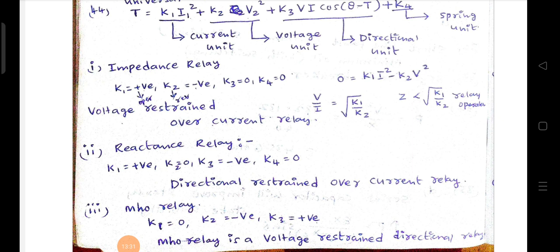Similarly, in case of reactance relay, K1 is positive, K2 is 0, K3 is negative. We consider K1 and K3 values. K3, the third term, indicates directional unit and is negative, meaning directional restrained. K1, the first term, indicates current. So for reactance relay, the relay used is directional restrained over current relay.